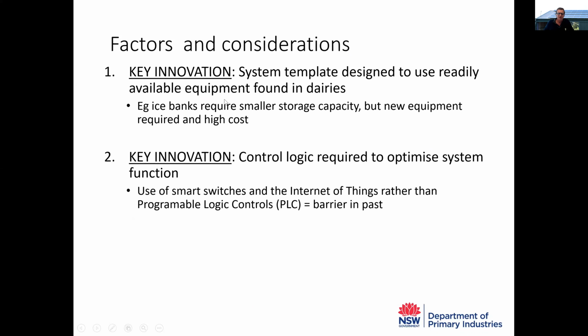There are a couple of key innovations in this program. The system template was designed to use readily available equipment found in dairies. Initially they looked at ice banks, which require a lot smaller storage, but the equipment required is quite different to what's readily available on dairies, it's unique to ice banks and has a very high cost. So the route taken was to use readily available equipment on farms.